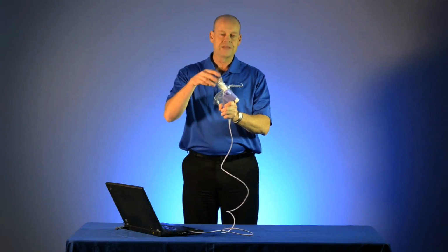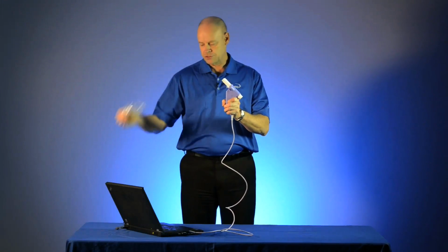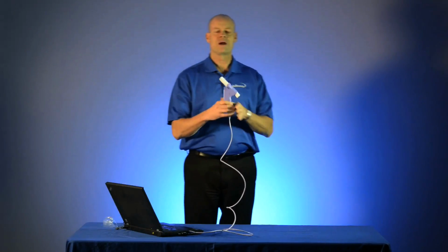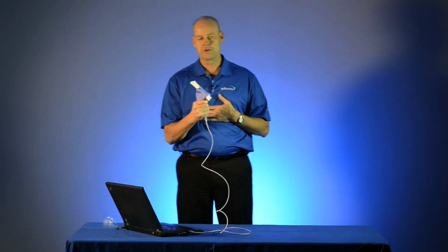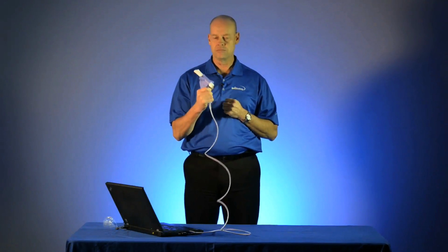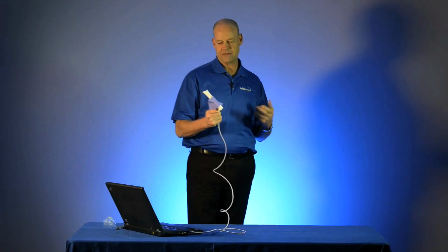So the technique is to remove the bag now that we're zeroed and good to go. And every spirometry test, no matter what spirometer you're using, requires a minimum of 3 blows. And you have to get 2 of the blows within 5% of each other based on the FVC and the FEV1. The FVC being the forced vital capacity and the FEV1 being the forced expiratory volume in the first second of the test. And each one of these tests is a maximum effort test. So it's critical that the person taking the test is giving you a maximum effort. So I'm going to demonstrate that for you now.